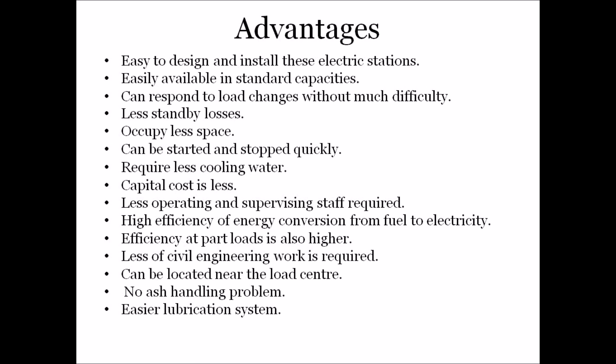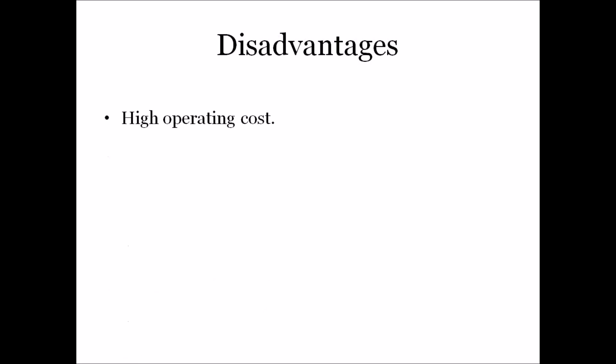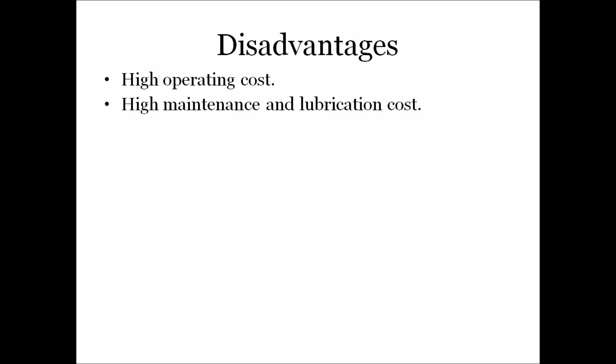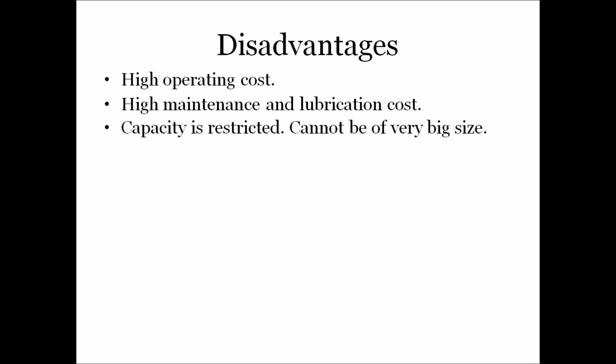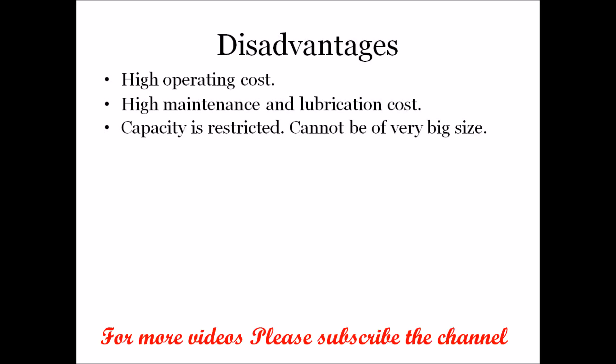There are several advantages of diesel electric power plants, but there are also some disadvantages. The main disadvantage is higher operating cost. The next is high maintenance and lubrication cost. The capacity is restricted — as mentioned earlier, the capacity is from 2 to 50 megawatts, so these cannot be installed for very high demand. There is also a noise problem.